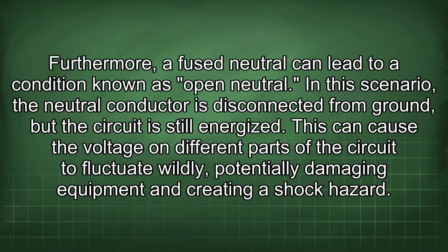Furthermore, a fused neutral can lead to a condition known as open neutral. In this scenario, the neutral conductor is disconnected from ground, but the circuit is still energized. This can cause the voltage on different parts of the circuit to fluctuate wildly, potentially damaging equipment and creating a shock hazard.